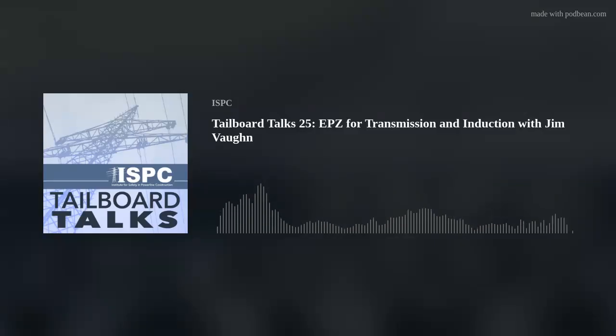And we've said before that we have had cases where we can describe it simply as the line worker was killed by the grounds that they installed for their own protection. So we came up with the cardinal rules of grounding, and we share those with our clients when we do training. So here's what the cardinal rules of grounding would say. When you make a ground connection, you make the ground source connection first. In other words, the ground electrodes. So whether it's the neutral, a ground rod, or a pole bond, you make that connection first.